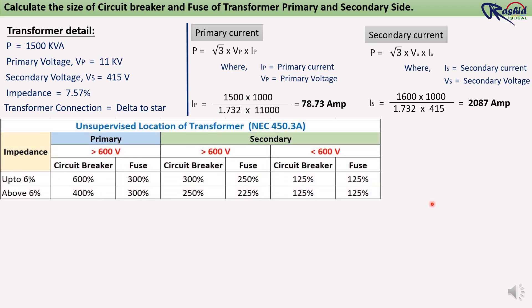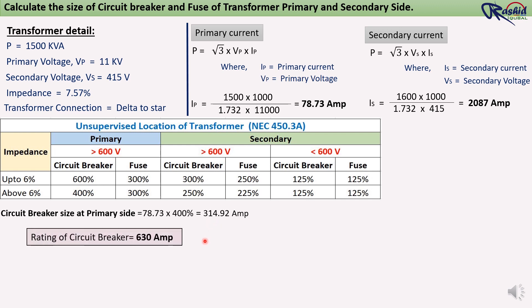As per the NEC standard, since the impedance is more than 6%, we follow this option. For circuit breaker calculation at the primary side, we multiply 400% by the primary current: 78.73 × 400% = 314.92 ampere. Since 314 ampere is not available, we go with the next bigger size of vacuum circuit breaker, which is 630 ampere — the minimum VCB available in the market.